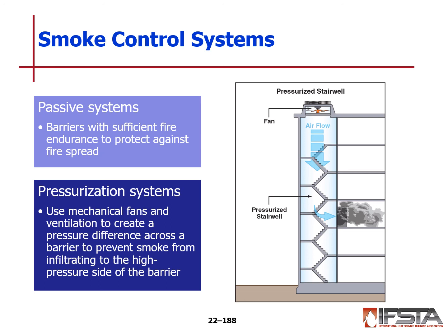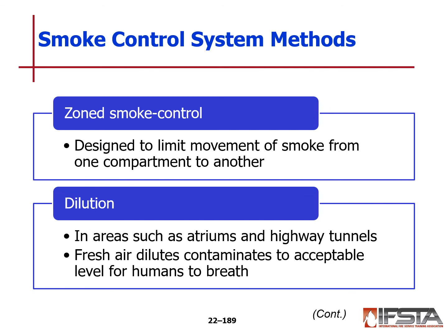Now, in buildings that do not have this, we do have older buildings and multi-story buildings that don't have these systems. Then we use our positive pressure ventilation fans, and we may even use more than one fan in tandem to achieve what one of these systems would do. We may use a zoned smoke control setup where it is designed to limit the movement of smoke from one compartment to the other. We can kind of get it to go where we need it to go. And dilution. This is in areas such as atriums and highway type tunnels where fresh air all at one time dilutes contaminants to an acceptable level for humans to breathe. We get that good air in, bad air out.